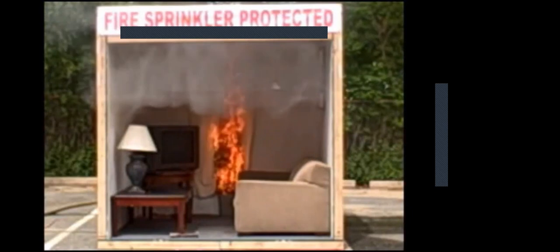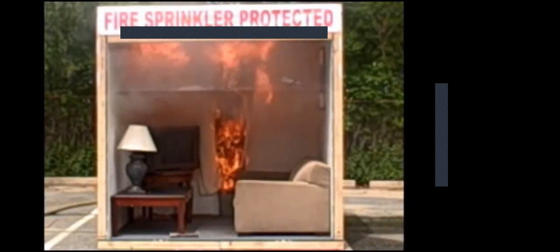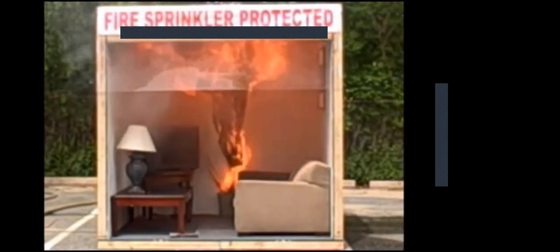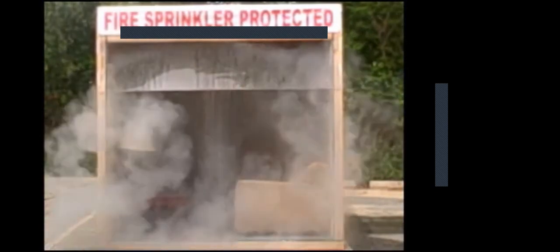We're about 25 to 30 seconds in now. And there goes the sprinkler. It activated. And the fire is well contained, probably out at this point. We're going to go ahead and shut down the sprinklers themselves now.